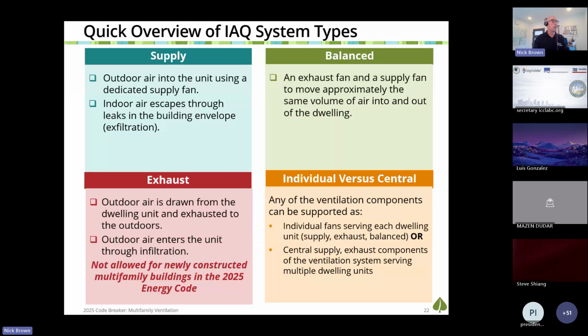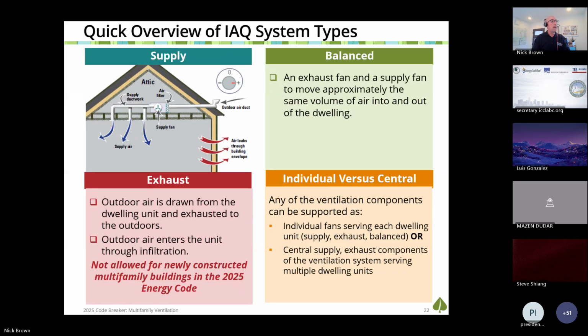possible options. In supply ventilation, outdoor air is brought in and pushed into the building using a supply air system that creates positive pressure in the building. And so the stale air leaks out through the building envelope. We're bringing in fresh air directly.